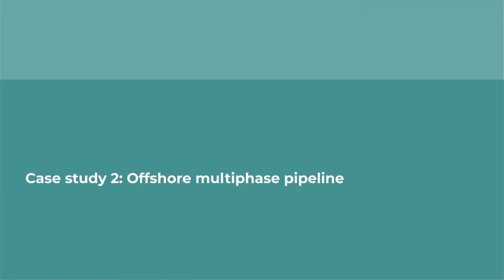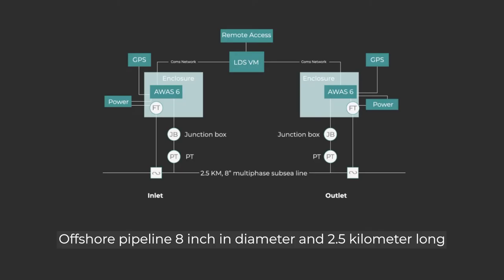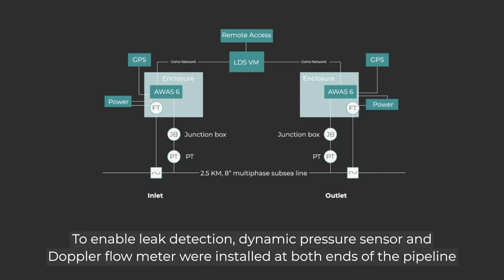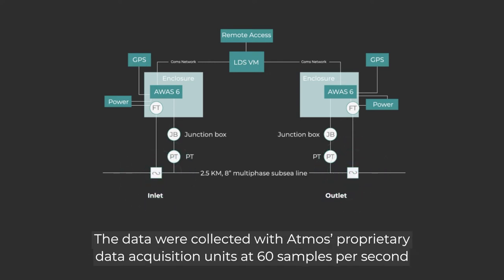Case Study 2: Offshore Multi-Phase Pipeline. An 8-inch diameter, 2.5-kilometer long offshore pipeline transports mostly oil and water with a small fraction of gas. There was no existing instrumentation on this pipeline. To enable leak detection, dynamic pressure sensors and Doppler flow meters were installed at both ends of the pipeline.